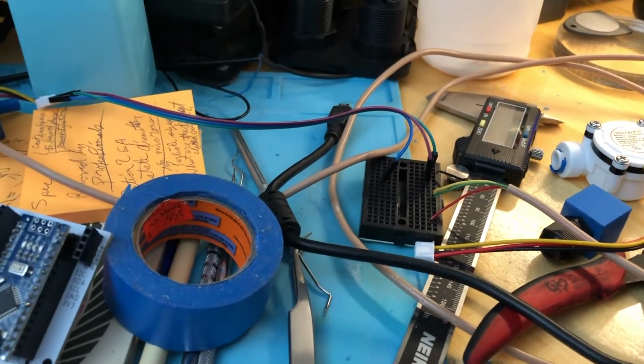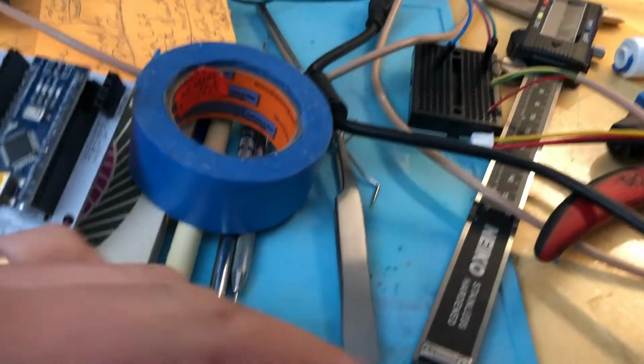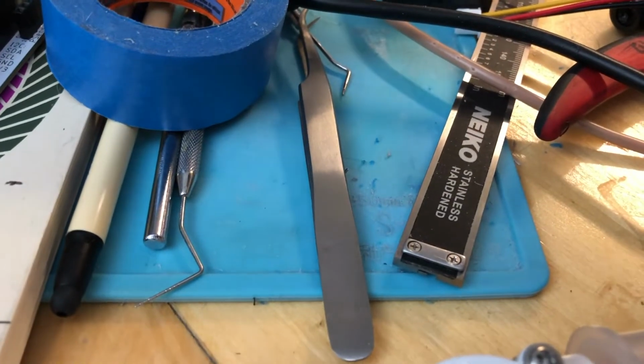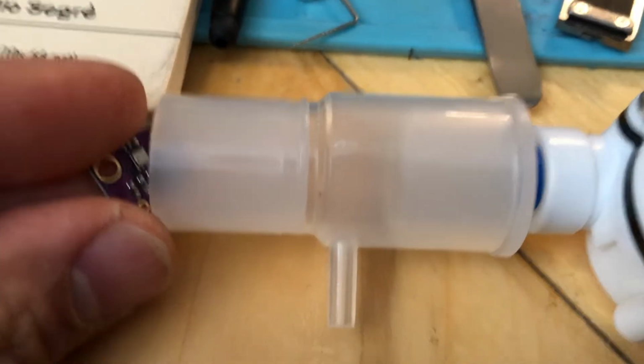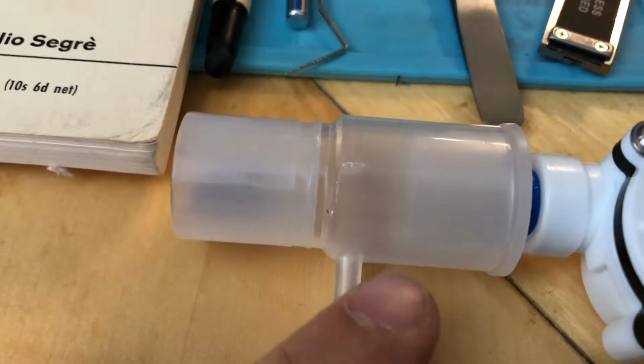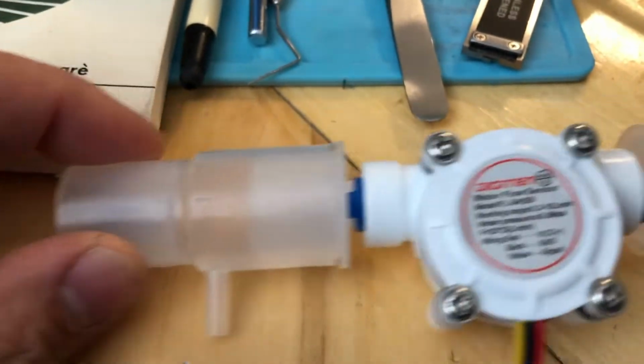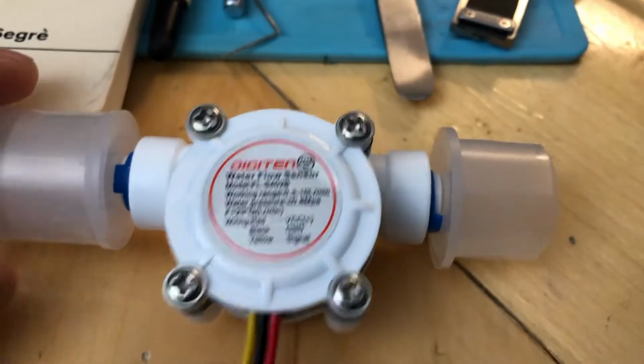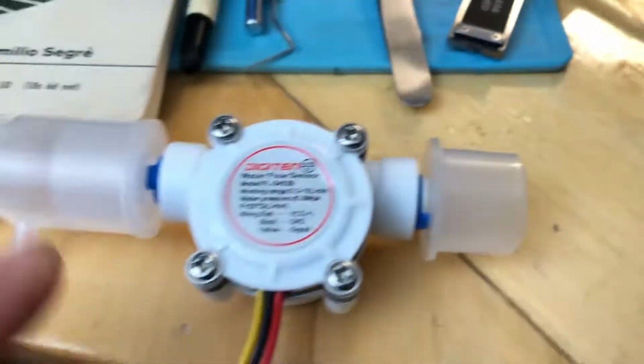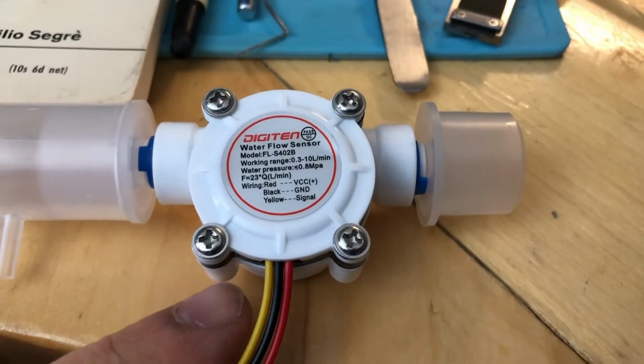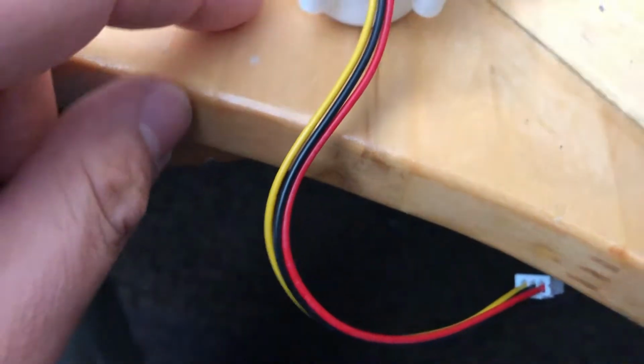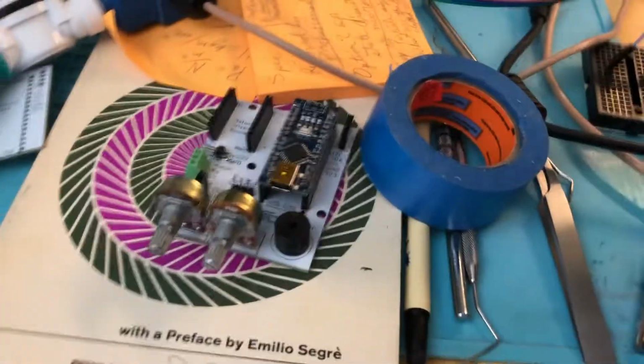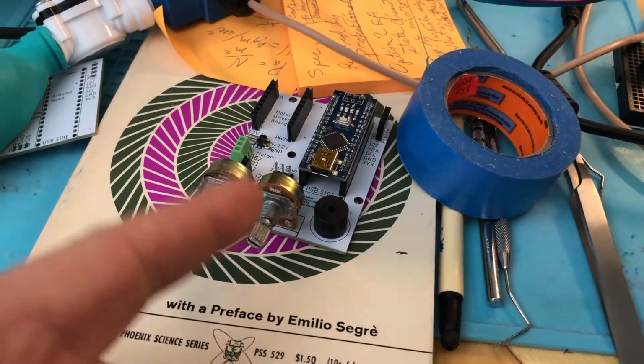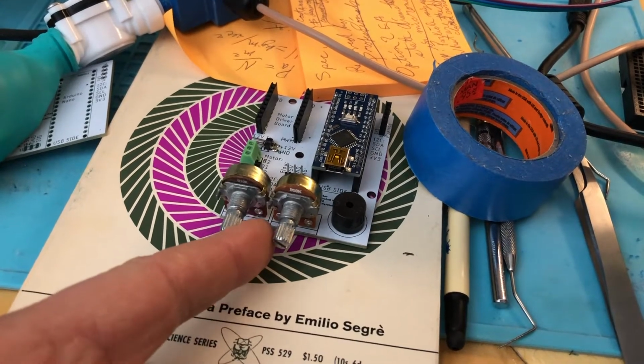Speaking of flow meters, the idea is that you'd have one of these pressure sensor boards inside here with the wires coming out of this little stem. This is a 22 millimeter standard respirator or respiration port, same on this side, and in between we have an inexpensive flow sensor giving a pulse width modulated output. That goes into here, and these two potentiometers you can adjust.